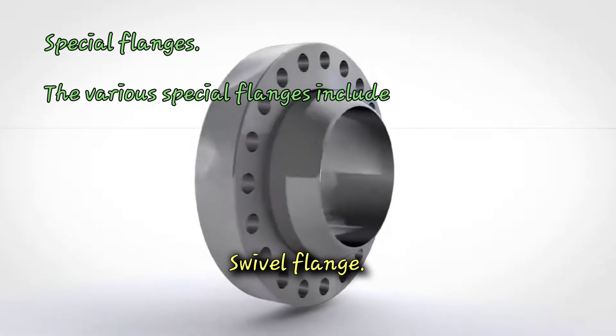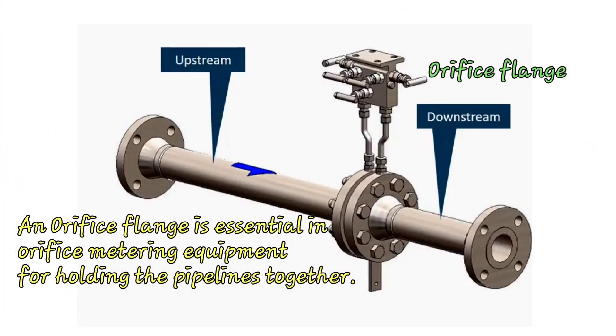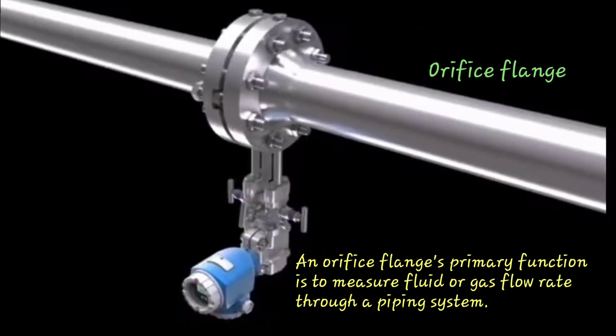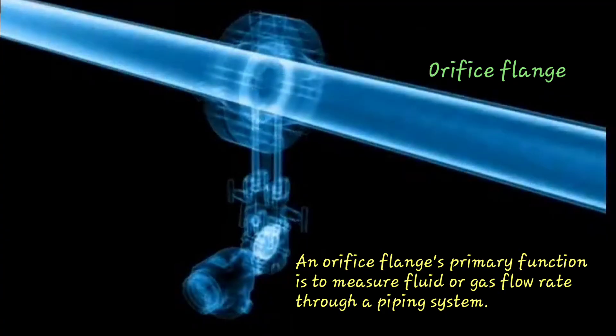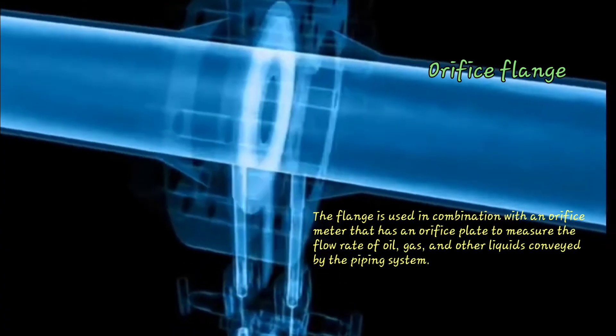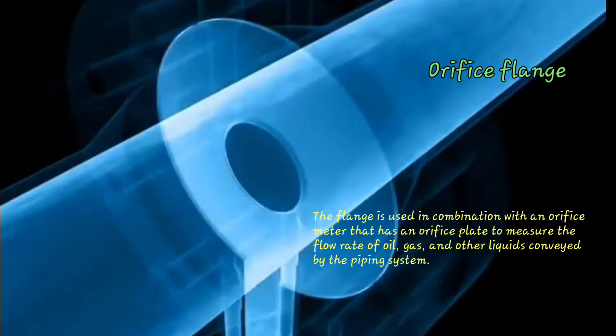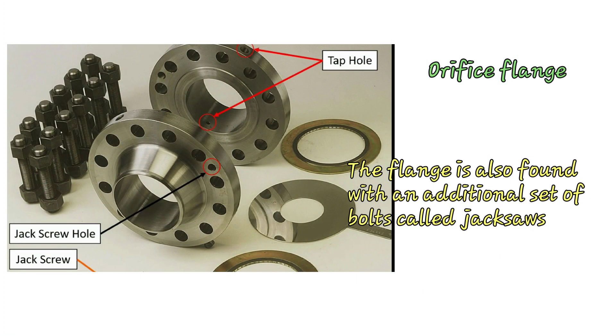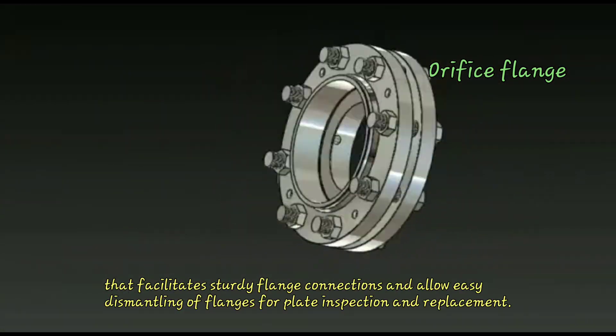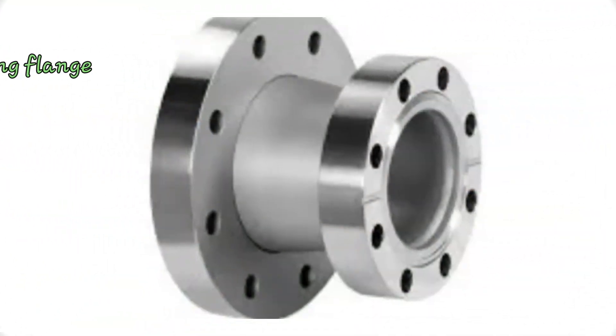Special flanges include the orifice flange, reducing flange, nepo flange, expanding flange, elbow flange, and swivel flange. The orifice flange is essential in orifice metering equipment for holding pipelines together. Its primary function is to measure fluid or gas flow rate through a piping system, used in combination with an orifice meter that has an orifice plate to measure the flow rate of oil, gas, and other liquids. The flange is also found with an additional set of bolts called jackscrews that facilitate sturdy flange connections and allow easy dismantling for plate inspection and replacement.